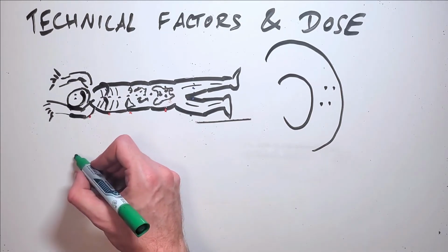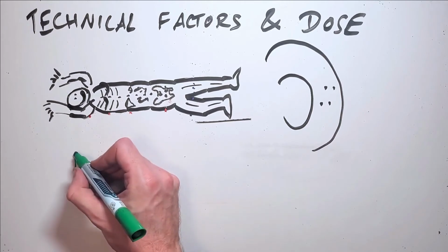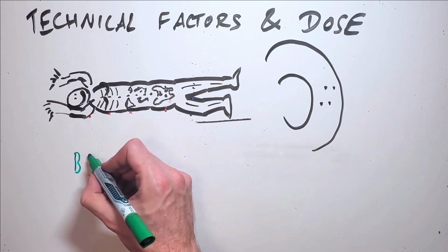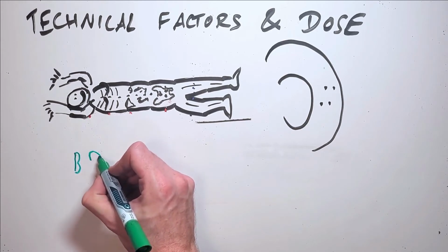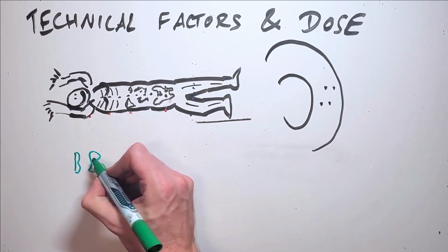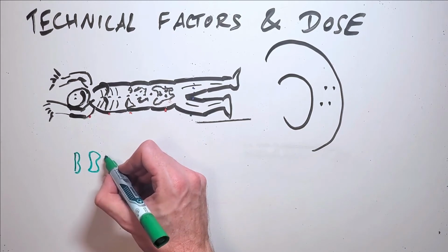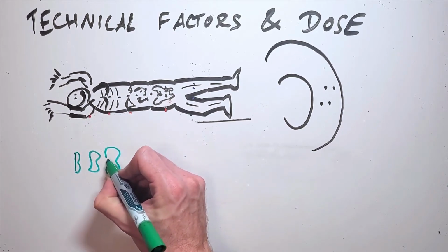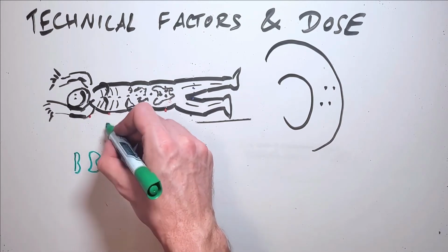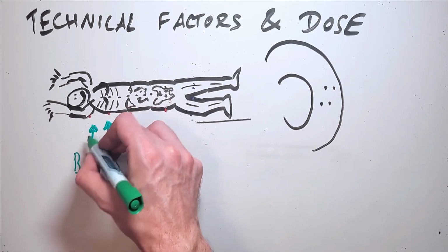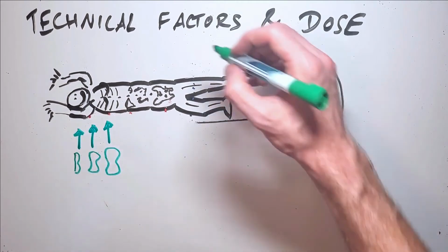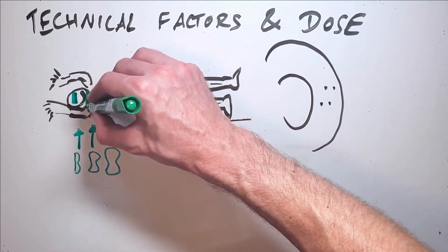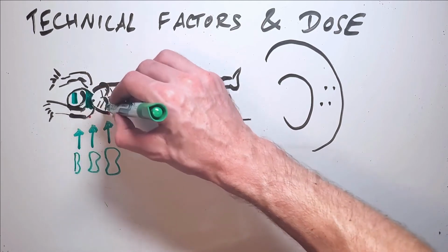As well as adapting our dose throughout the length of the Z-axis, we can also use a few dose reduction techniques to reduce the entrance dose just at the anterior surface of the patient, where radiosensitive organs like the breast, thyroid, and eyes are. In some cases, bismuth shielding can be placed over these areas to absorb low energy photons entering them, while still allowing normal dose distribution to the remaining tissues. It's important to add these shields after acquiring the scout images, because otherwise they will be detected in the scout images and the software will simply increase the dose to compensate for them.